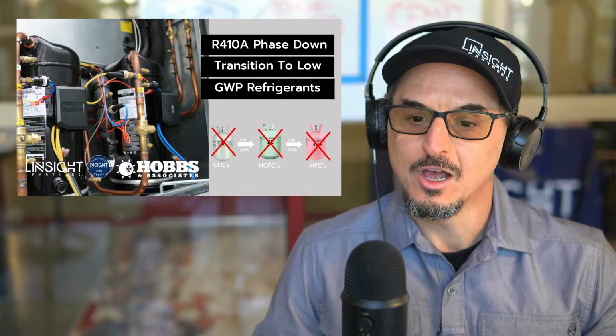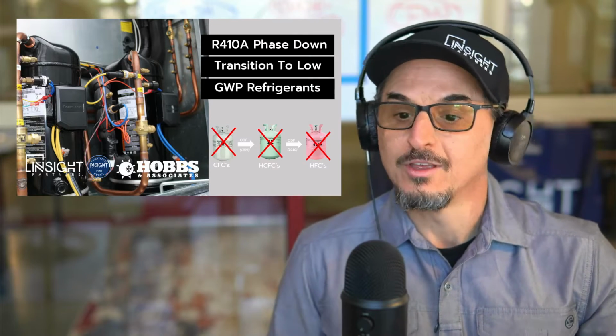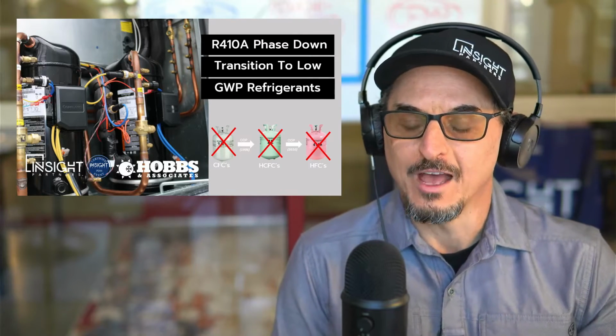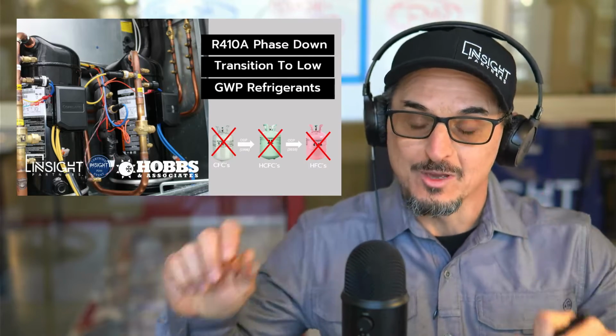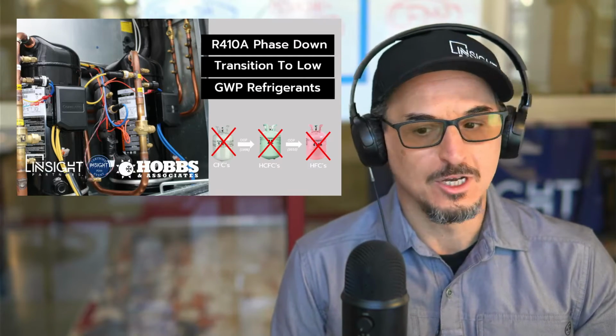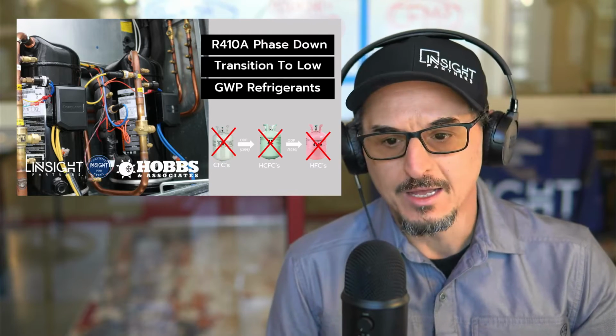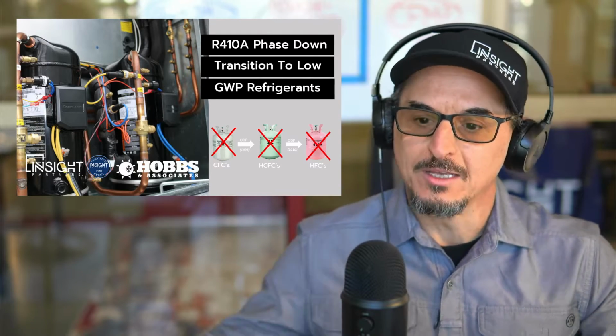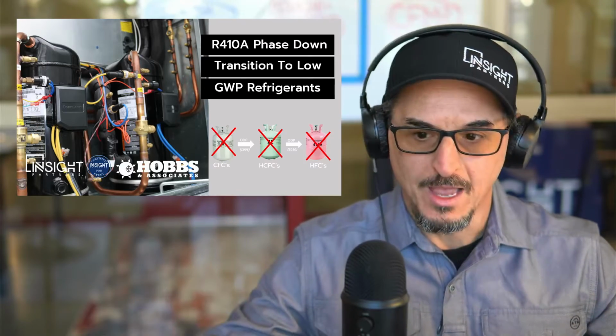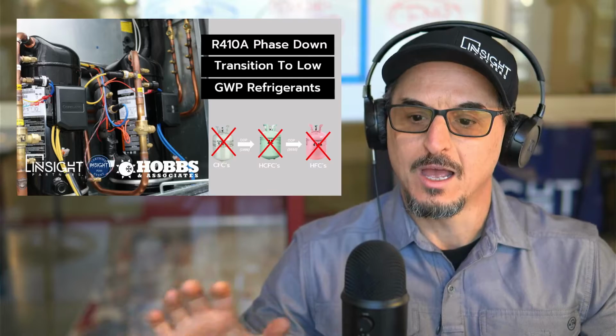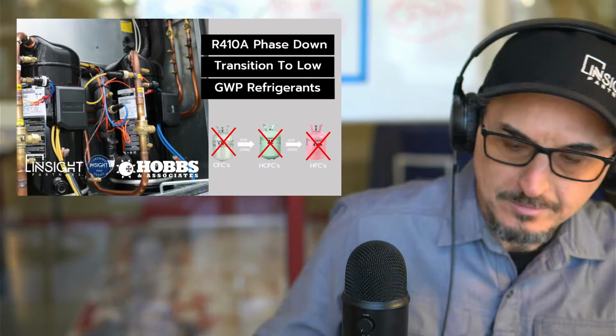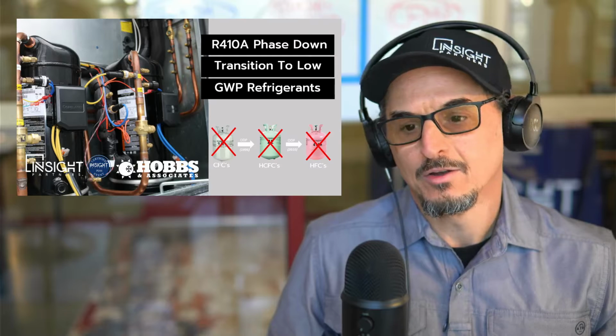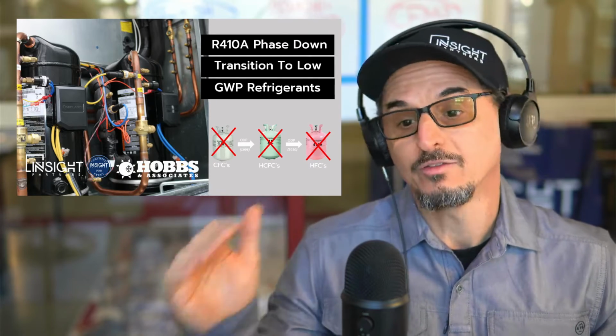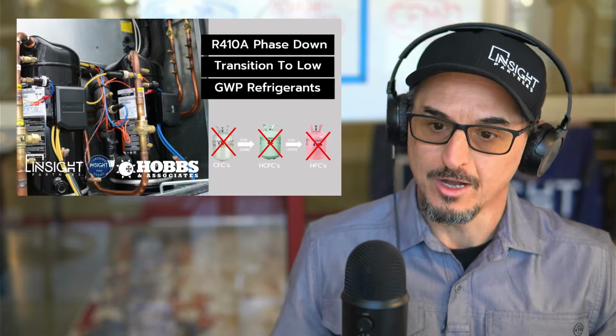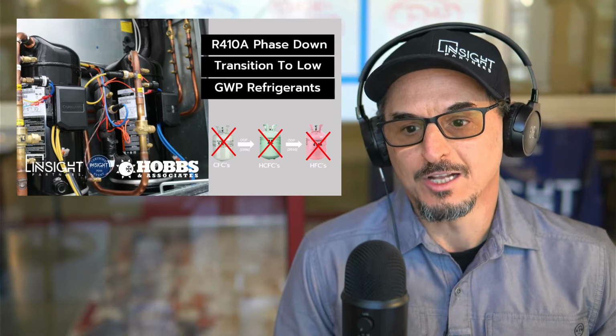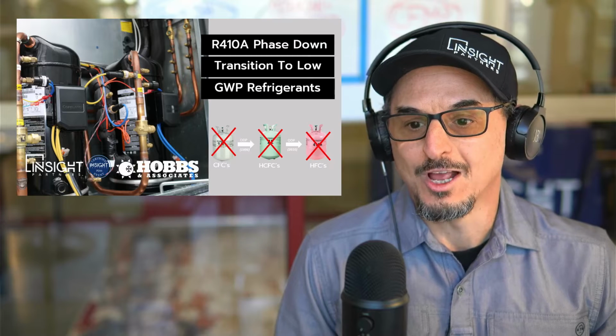The first thing to note is that it's technically not an R410A phase down. It's a high GWP refrigerant phase down. GWP is global warming potential. What's happening is the EPA, through the AIM Act—Congress gave EPA the tools to limit refrigerants to a GWP of 700. So that's really what it's all about. It's not specifically targeting 410A, it's targeting any refrigerant above 700.